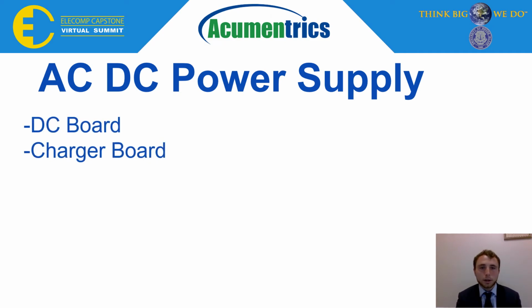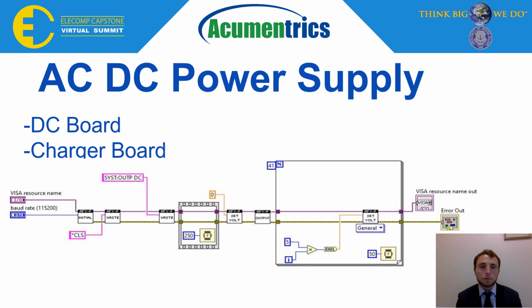This is the DC board and charger board AC/DC power supply VI. Start off by initializing the AC and DC power supply so LabVIEW knows which unit is being tested. From there, we use SCPI commands to clear and set the output DC voltage to 0. From there, the voltage ramps up 5 volts every 50 milliseconds for 41 times, bringing the voltage to 200 volts safely.